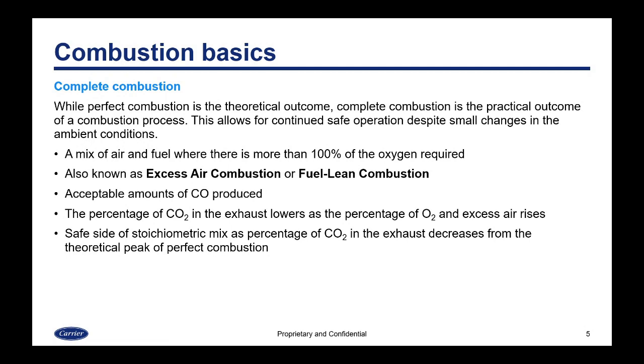While perfect combustion is the theoretical outcome, complete combustion is the practical outcome of a combustion process. This allows for continued safe operation despite small changes in ambient conditions. It's a mix of air and fuel where there is more than 100 percent of the oxygen required, also known as excess air combustion. With complete combustion there will be CO but in acceptable amounts. The percentage of CO2 in the exhaust begins to get lower as the percentage of O2 and excess air rises.